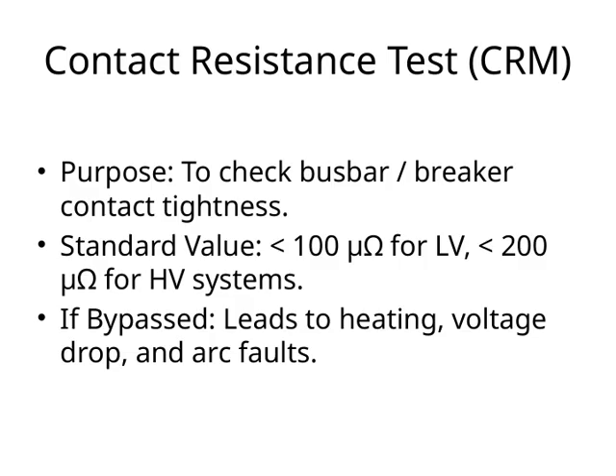These thresholds help us determine if the contacts are performing properly. It's also important to note what happens if this test is bypassed or if the contact resistance exceeds these limits. Bypassing or having high resistance can cause heating at the connection points, which is a serious risk. It can also lead to voltage drops that affect system performance, and in worst cases, arc faults that could cause equipment damage or safety hazards.